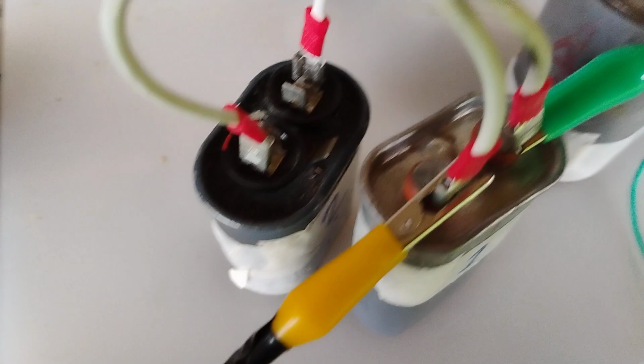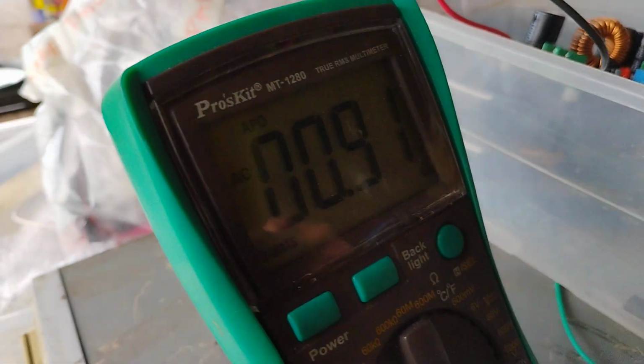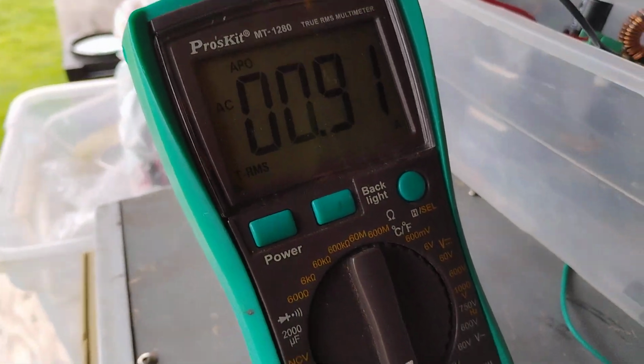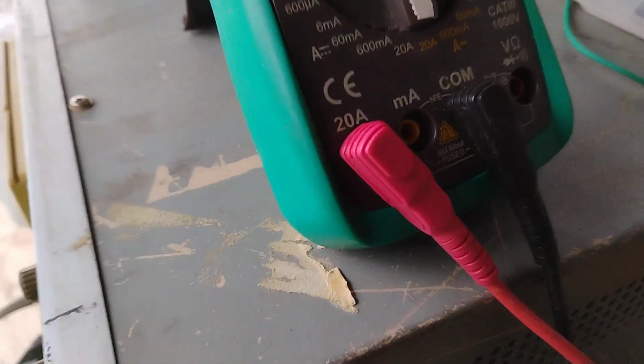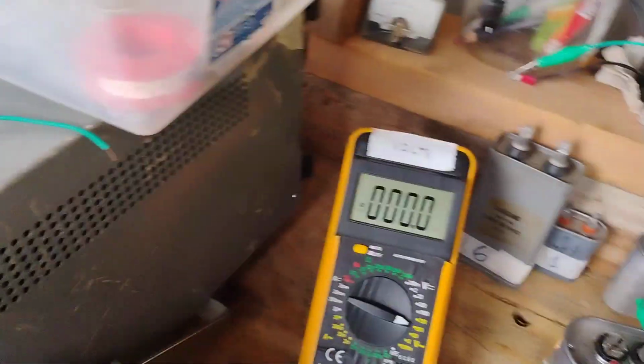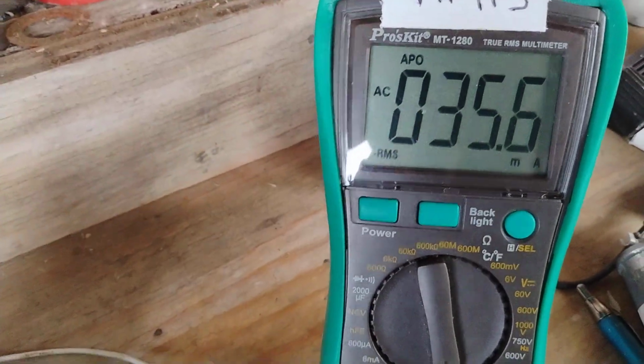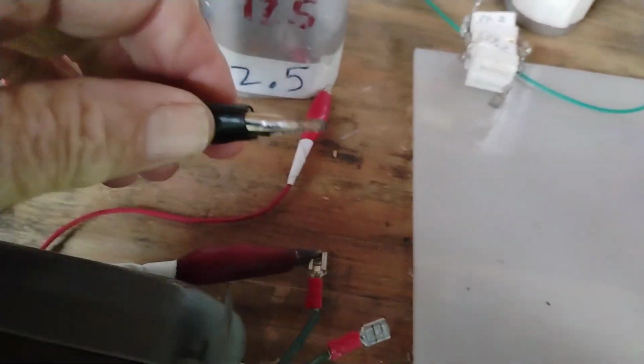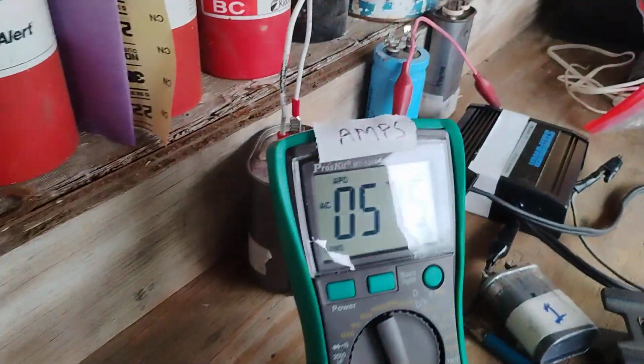For the 3 UF run cap, not a 4 which I just did, 3 UF gives you 0.91 amps, almost an amp in AC coming out. Not bad. And look at how much the draw has gone down while shorted. Now if it's not shorted on the secondary side, not shorted, it goes all the way up to 57.